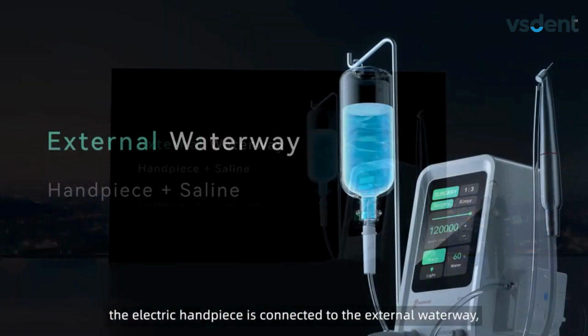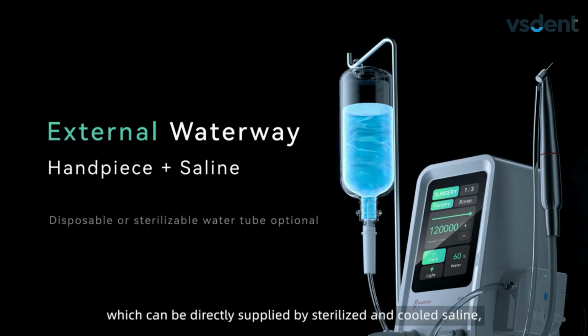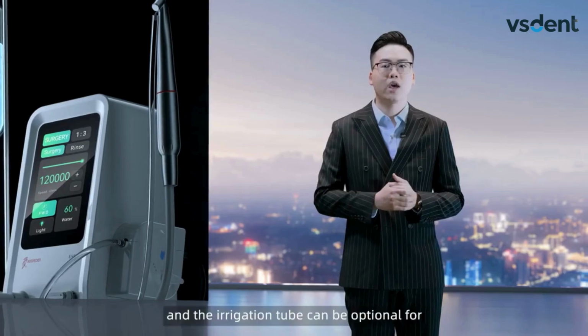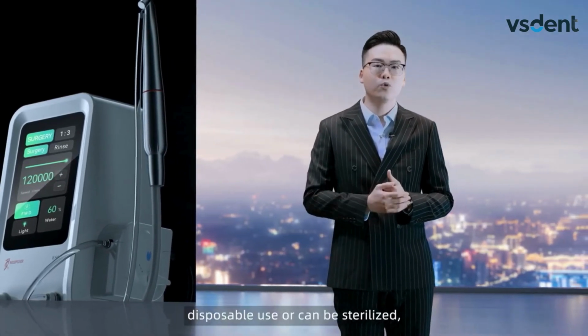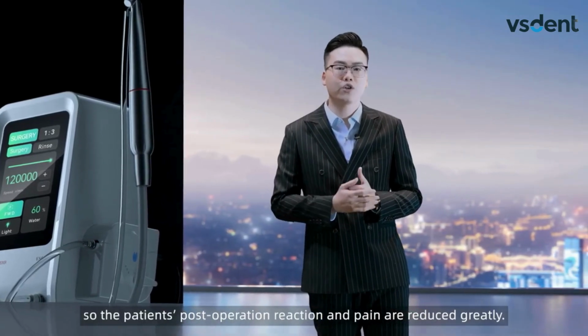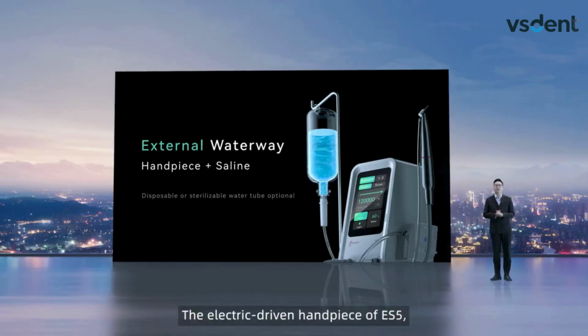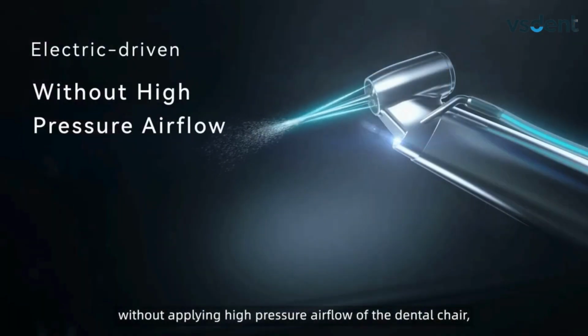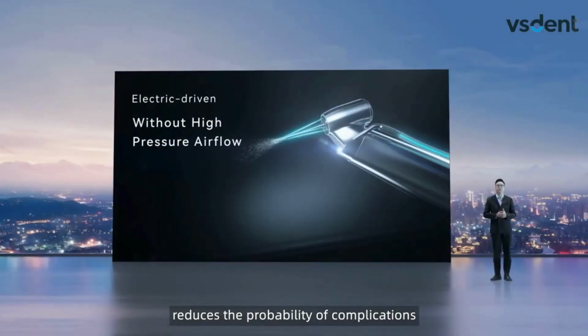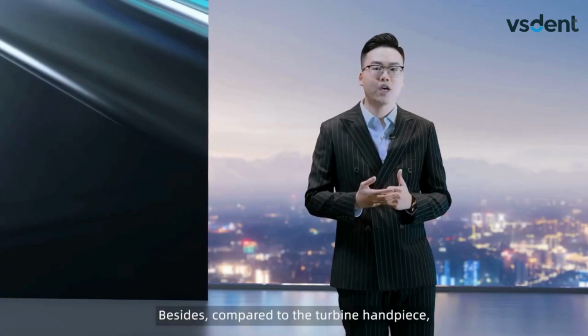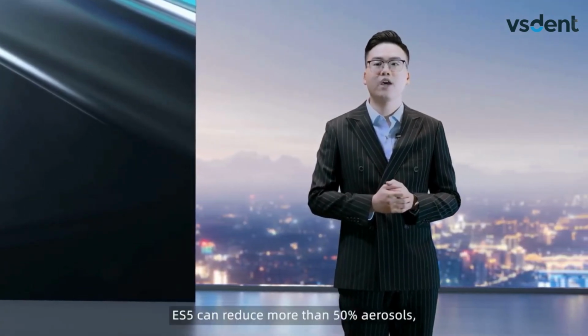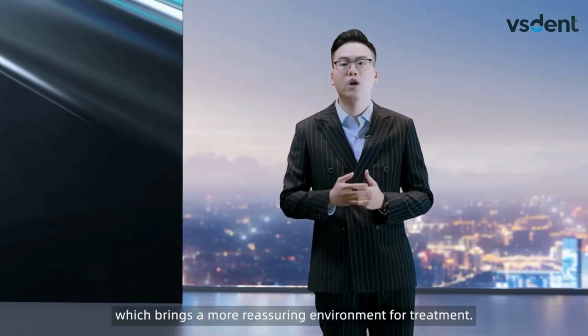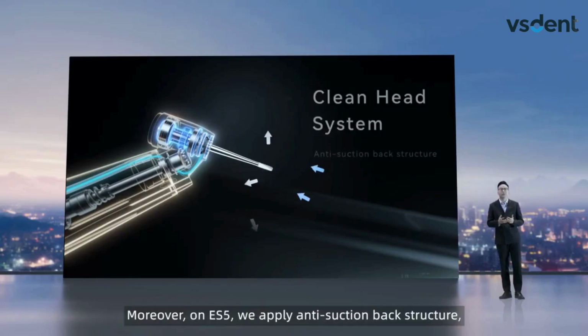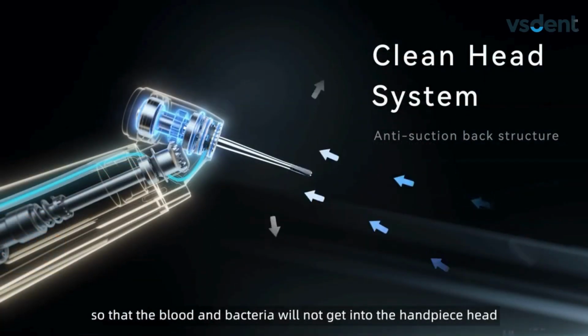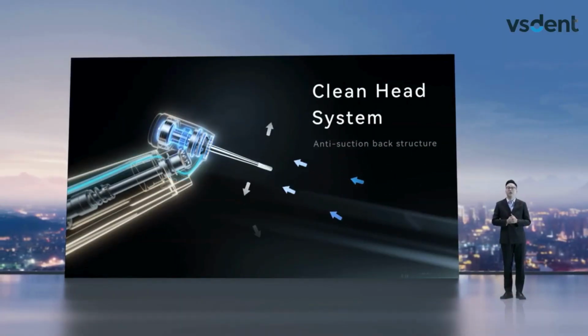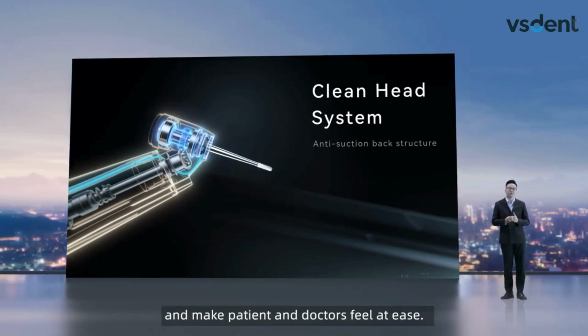Under its surgical mode, the electric handpiece is connected to an external waterway, which can be directly supplied by sterilized and cooled saline. And the irrigation tube can be optional for disposable use or can be sterilized, so the patient's post-operation reaction and pain are reduced greatly. The electric-driven handpiece of ES5 does not apply any pressure airflow from the dental chair, which reduces the probability of complications such as post-operation emphysema. Besides, compared to the turbine handpiece, ES5 can reduce more than 50% of aerosols, which brings a more reassuring environment for treatment. Moreover, on ES5, we apply an anti-suction back structure so that the blood and bacteria will not get into the head of the handpiece. Thus, it avoids cross-infection and makes patients and doctors feel at ease.